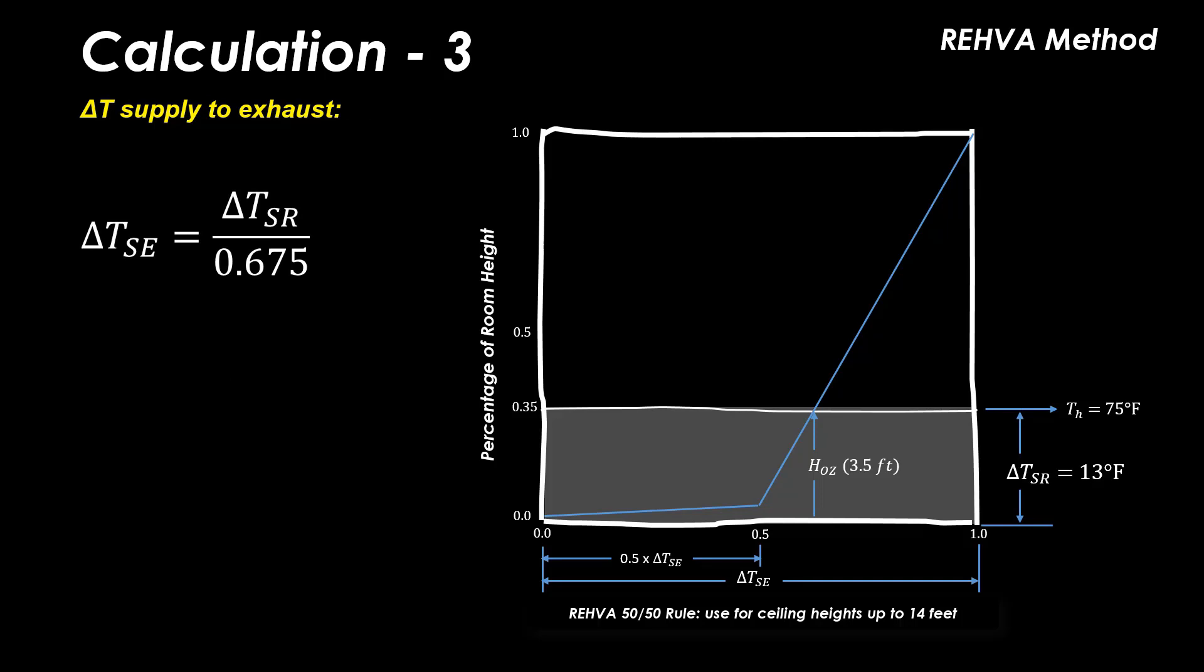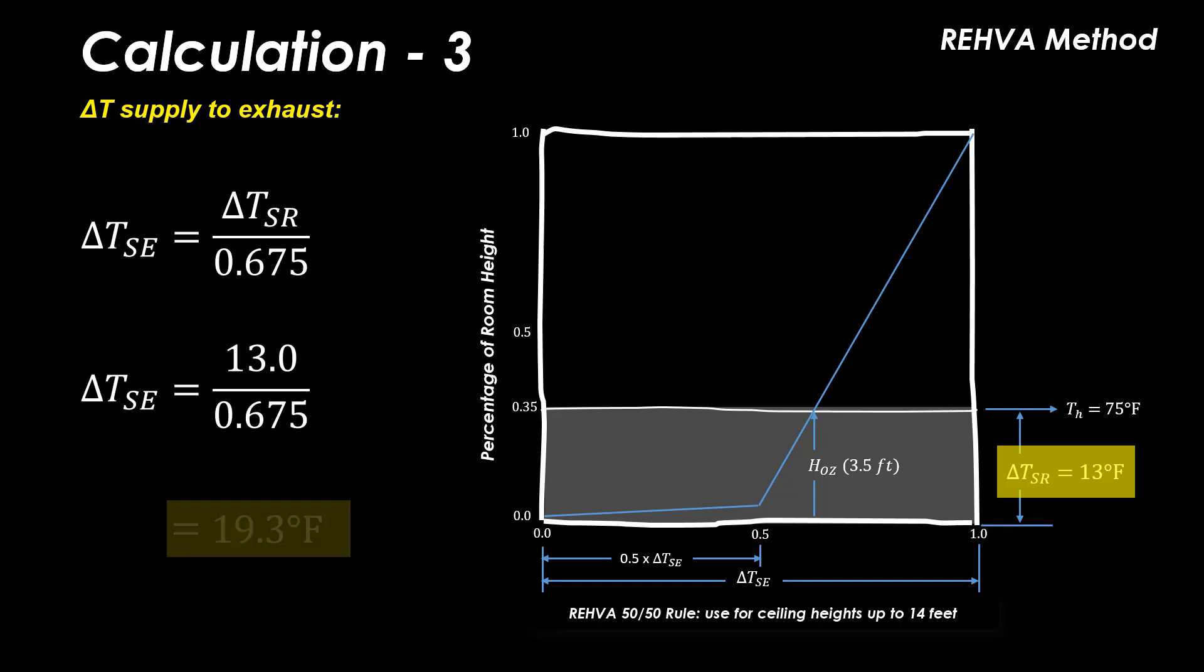Using the percentage of temperature gradient from the supply air outlet to head height, we can now calculate the exhaust or return air temperature differential, which is delta TSE by dividing delta TSR from calc 1 by 0.675. The result is 19.3°F.